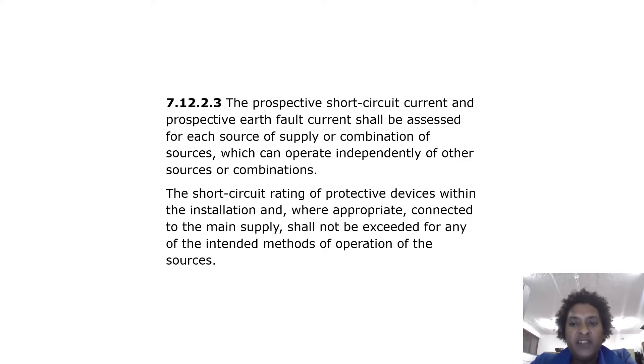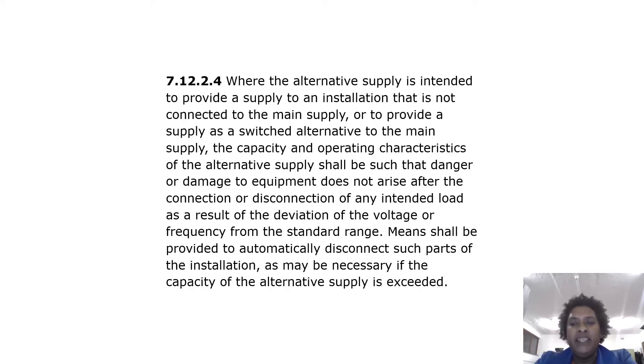The short circuit rating of protective devices within the installation, and where appropriate connected to the main supply, shall not be exceeded for any of the intended methods of operation. Where the alternative supply provides supply to an installation not connected to the main supply, or as a switched alternative, the capacity and operating characteristics shall be such that danger or damage to equipment does not arise. Means shall be provided to automatically disconnect parts of the installation if the capacity of the alternative supply is exceeded.